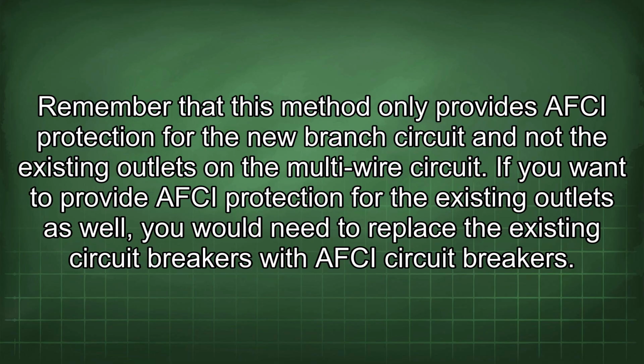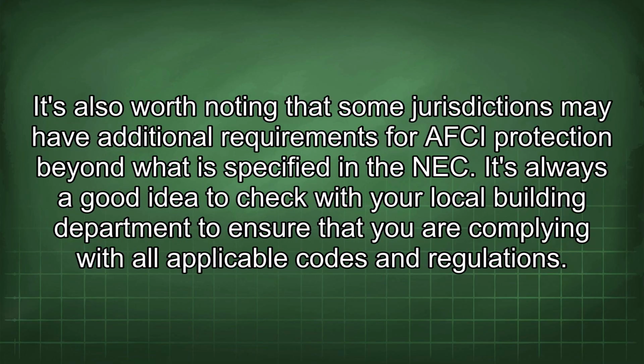Remember that this method only provides AFCI protection for the new branch circuit and not the existing outlets on the multi-wire circuit. If you want to provide AFCI protection for the existing outlets as well, you would need to replace the existing circuit breakers with AFCI circuit breakers. It's also worth noting that some jurisdictions may have additional requirements for AFCI protection beyond what is specified in the NEC. It's always a good idea to check with your local building department to ensure that you are complying with all applicable codes and regulations.